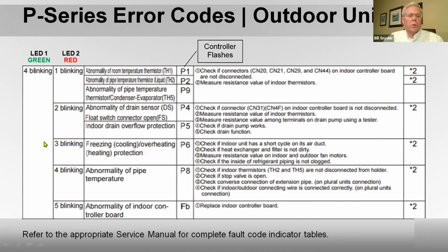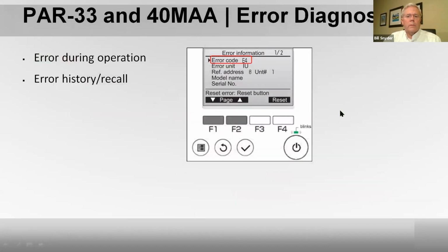On the P series, you also have what's called LED 1 and LED 2, a green and a red light. If the green light is blinking 4 times and the red one is blinking 1 time, that might mean that you've got a bad thermistor. If you had the controller hooked to it, the controller is probably going to give you a P1 fault code, and it's going to tell you to look at these connectors on the board. So we kind of steer you to the right connection.